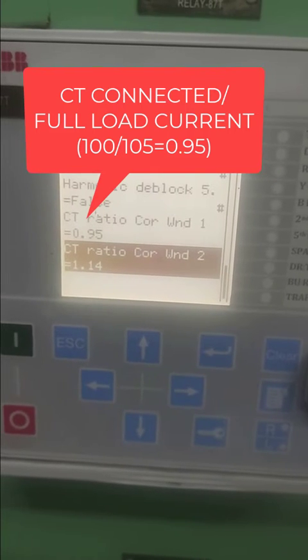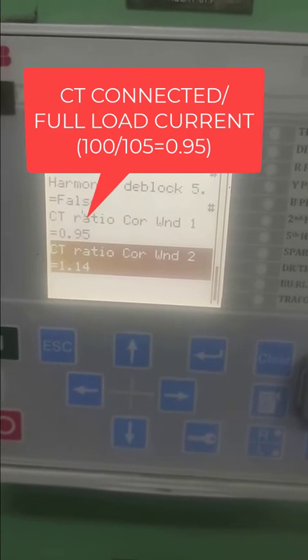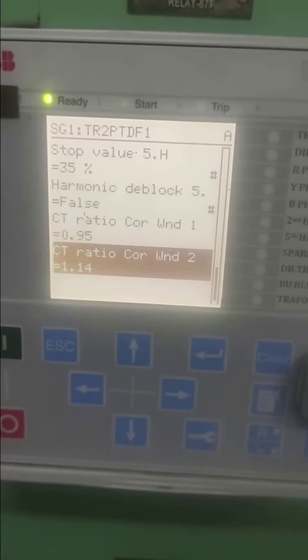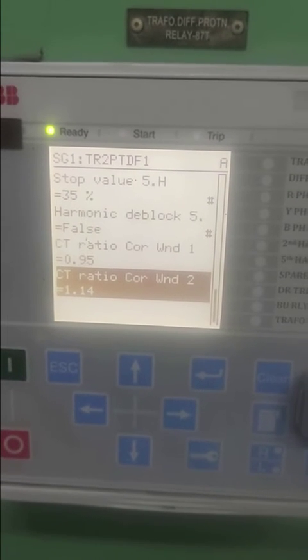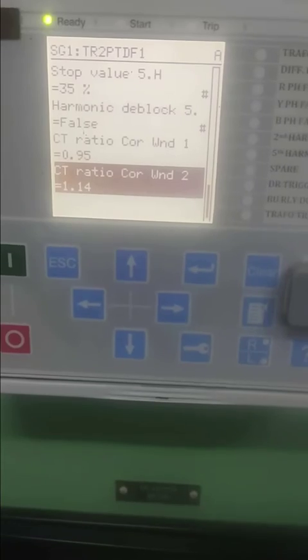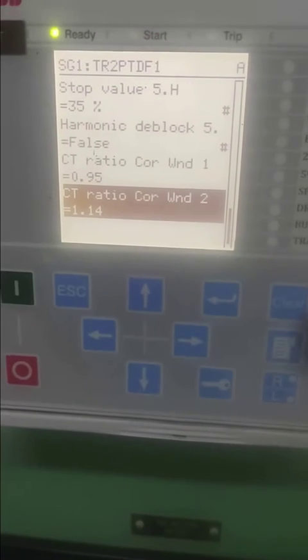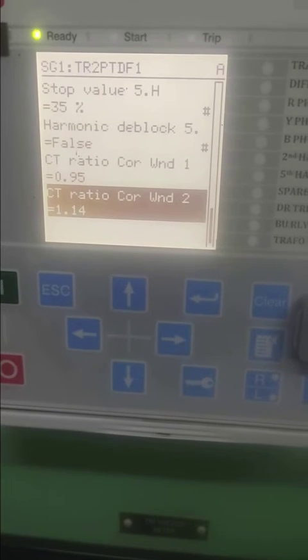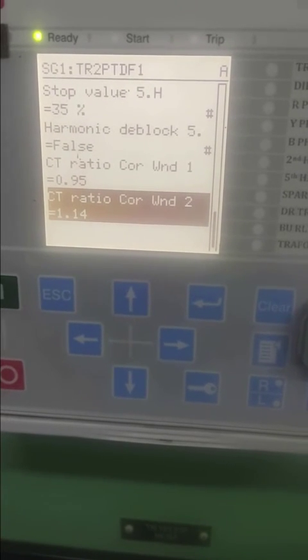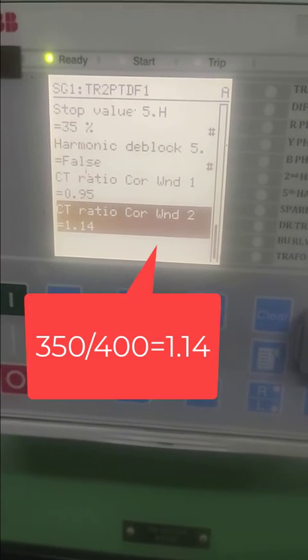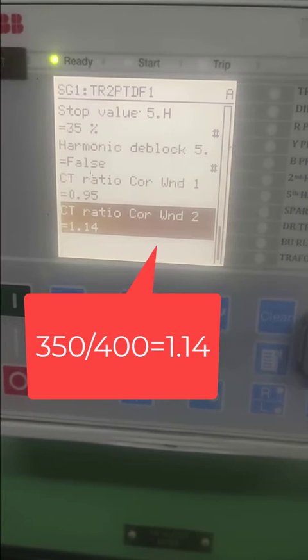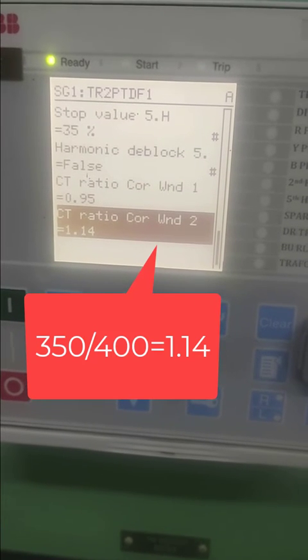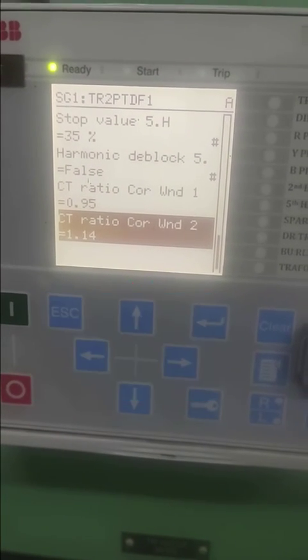Similarly for winding two, we have 400 connected for all cores and the full load amp for the LV winding is 350 amps. So 350 by 400 gives you 1.14 amps. This is a very short video just to view the settings and understand the CT correction and CT ratio.